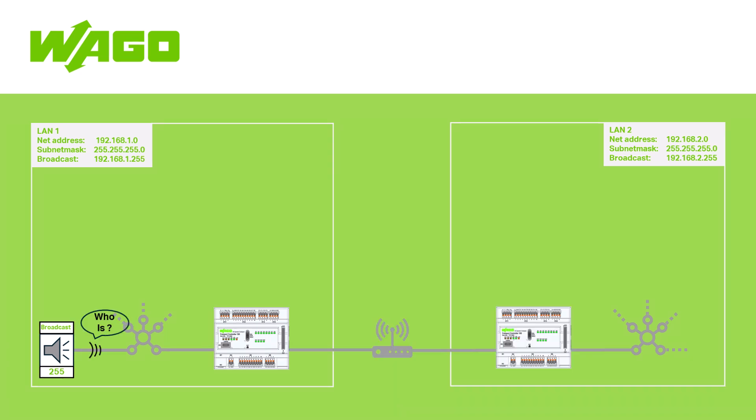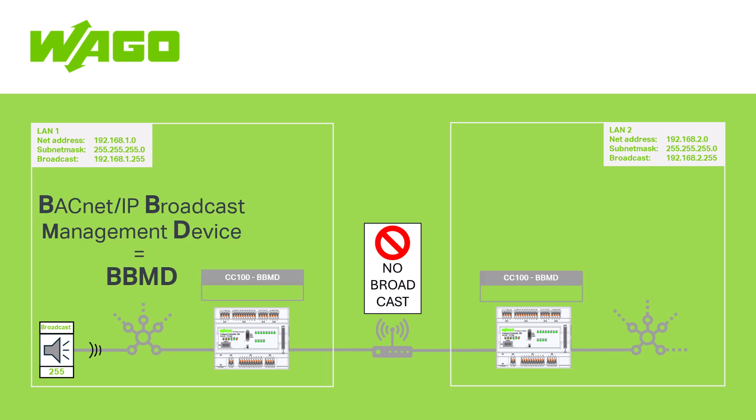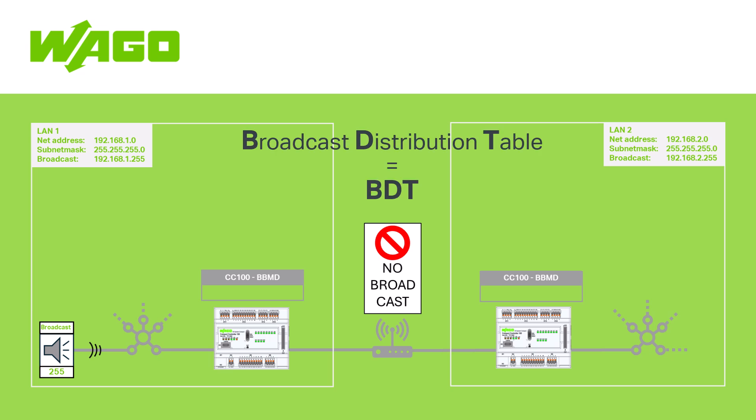However, broadcast messages are not allowed through IP routers and are blocked. This means that BACnet communication across different subnets is not easily possible. To overcome this problem, the BACnet broadcast management device was introduced. A device is then configured as a BBMD in a local network, which then forwards IP broadcast messages to remote IP subnets based on a broadcast distribution table. To avoid communication conflicts, there should only be one BBMD in each IP subnet.